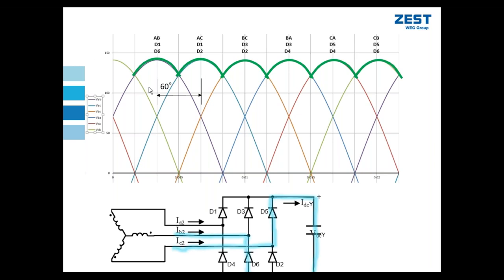What's interesting to note here is that for the period of one cycle, you have six pulses that are the let-through voltage to your DC link. So on the output of your bridge rectifier, if this was a purely resistive load, and at the moment it's showing a capacitor, that green six pulse rippled waveform would be what your DC link voltage would look like. Okay. But we don't have a resistive load in a variable speed drive.